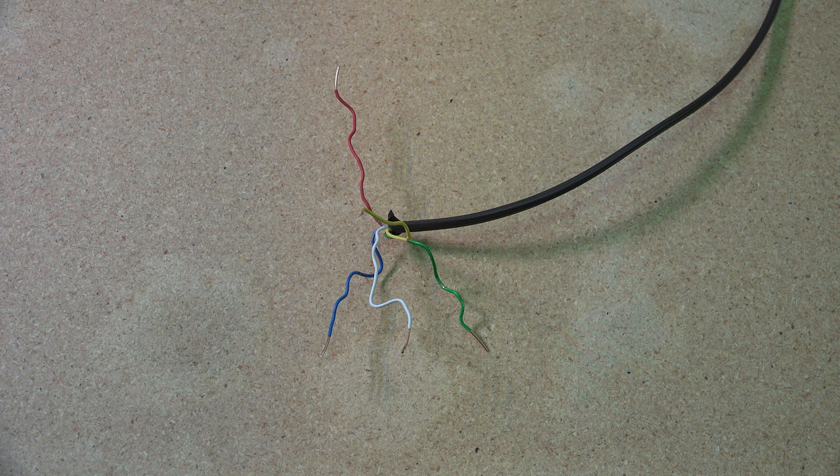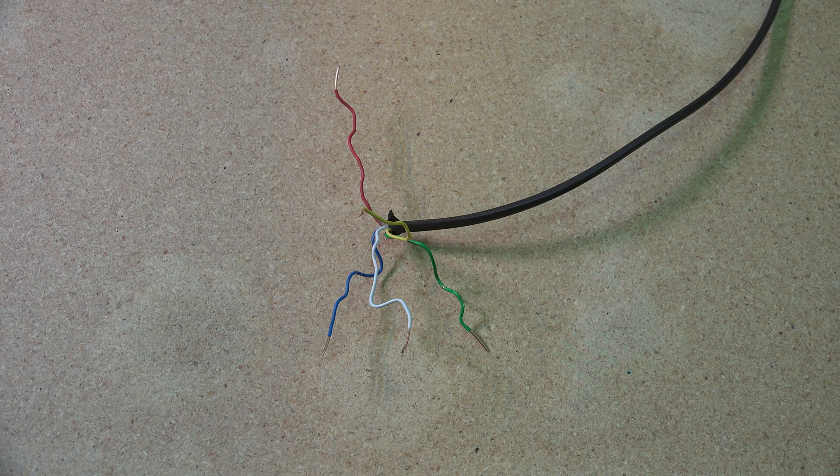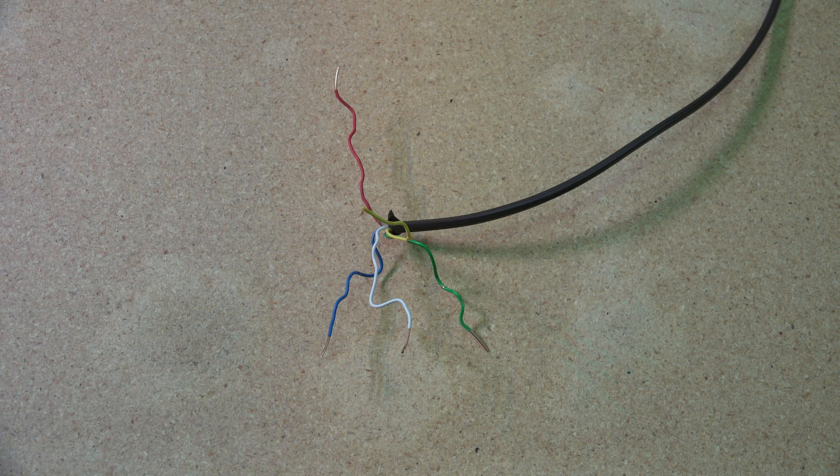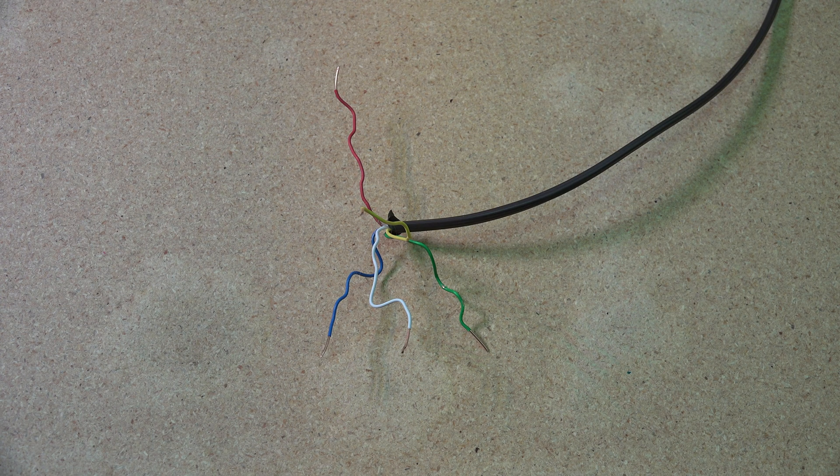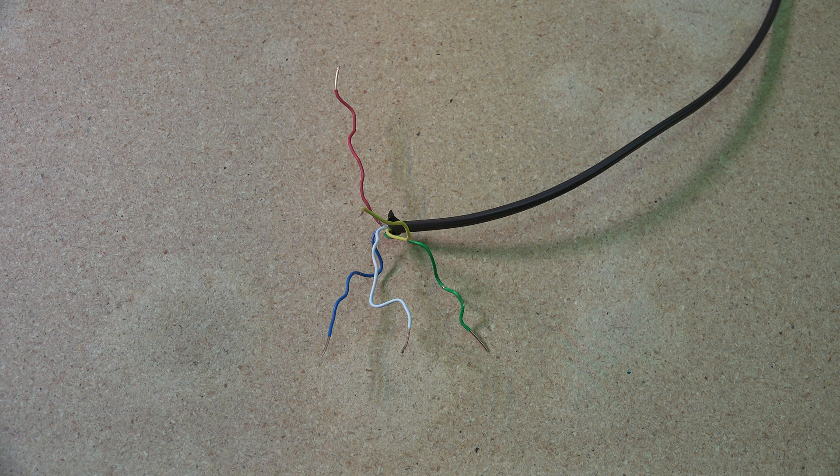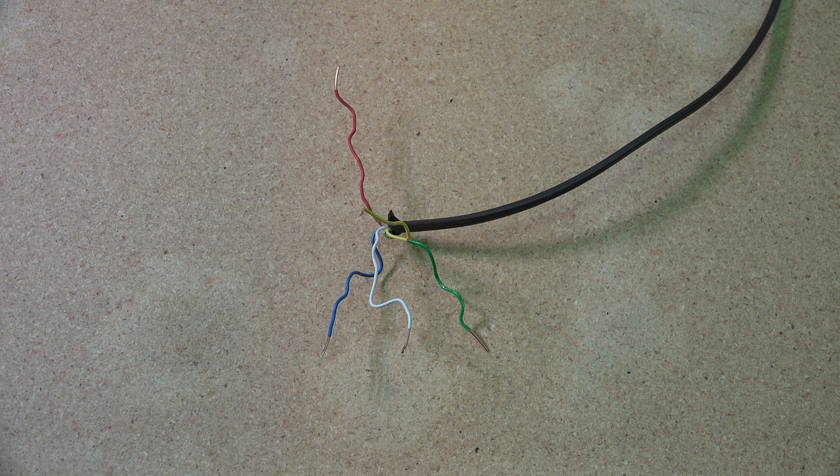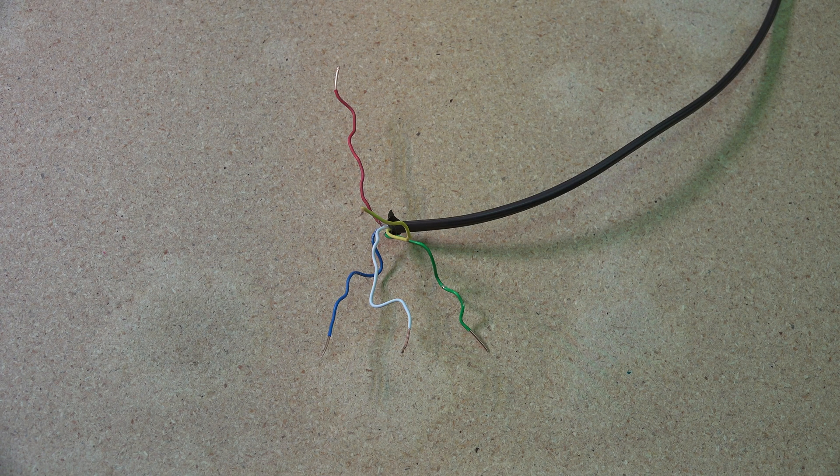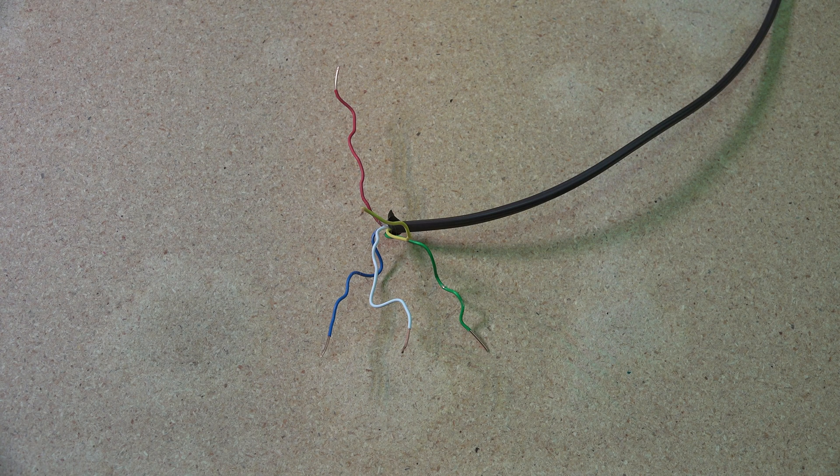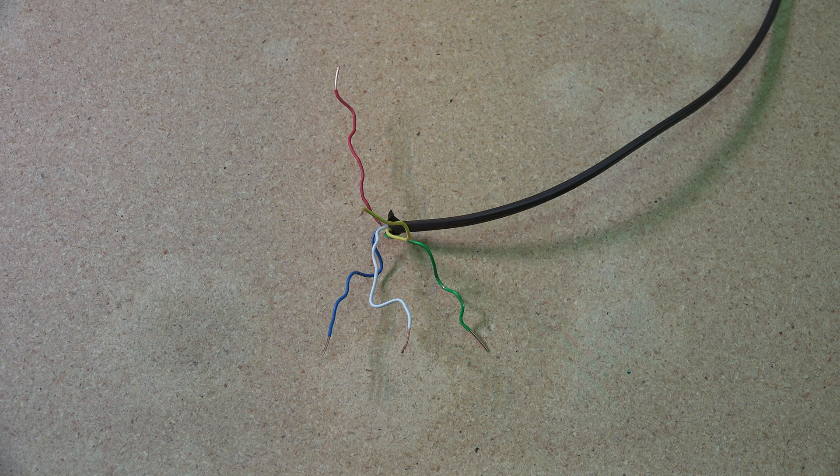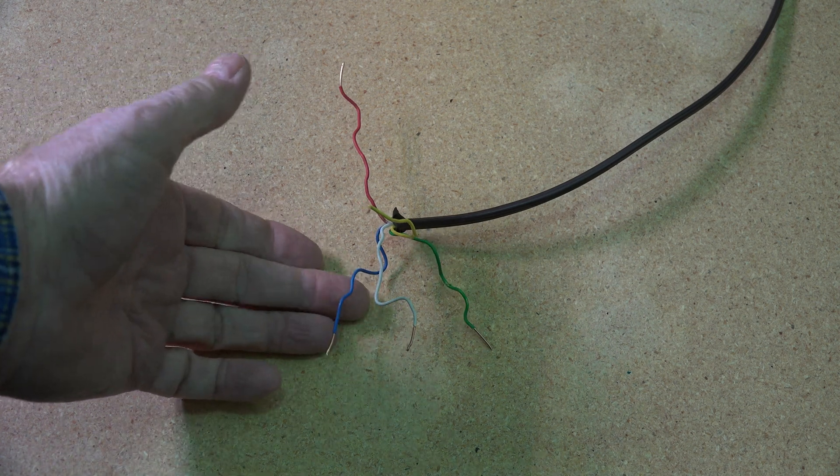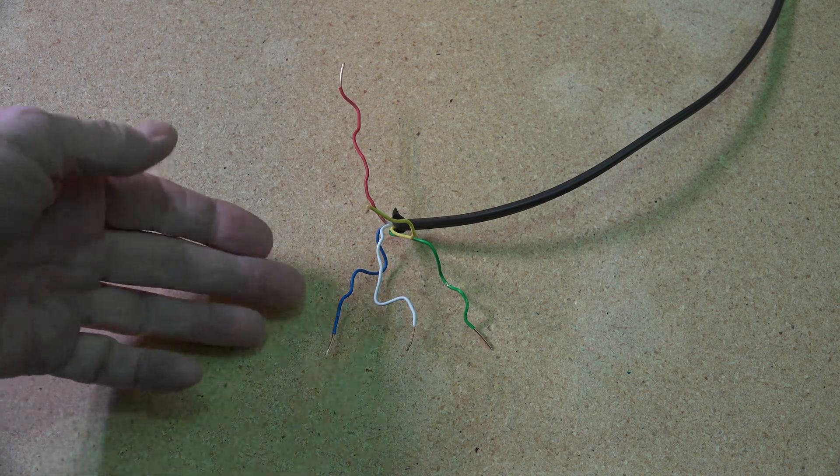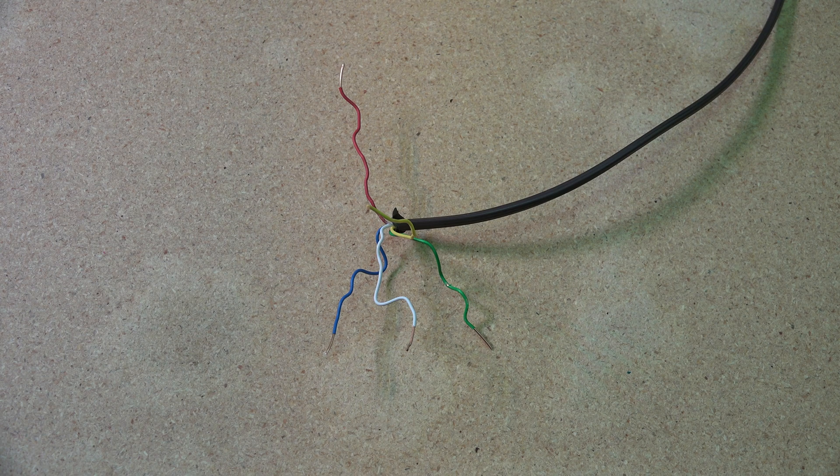So I've got to replace thermostat wire, right? Well, not necessarily. You could have a broken wire in the wall - somebody put a staple through it or something, I've had that happen. But there's a really good chance that any problem with thermostat wire is going to be on the ends like this right here.